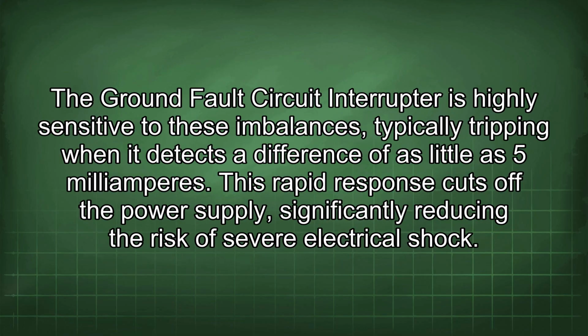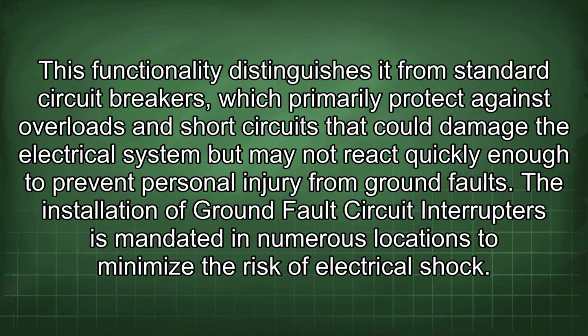The ground fault circuit interrupter is highly sensitive to these imbalances, typically tripping when it detects a difference of as little as 5 mA. This rapid response cuts off the power supply, significantly reducing the risk of severe electrical shock. This functionality distinguishes it from standard circuit breakers, which primarily protect against overloads and short circuits that could damage the electrical system but may not react quickly enough to prevent personal injury from ground faults.